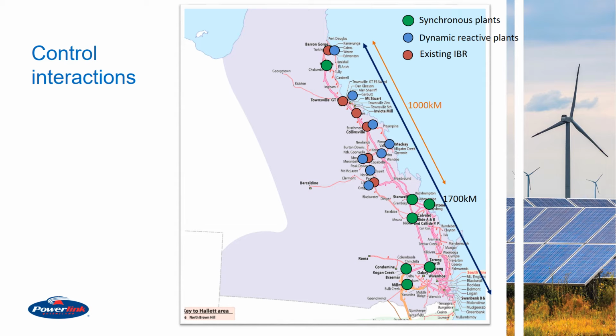One of the main issues that we have seen in Queensland due to low system strength, and that is not really any different from rest of the NEM, is the control interactions. What it means is that all those inverter-based plants interact with each other and cause some sort of instabilities. When we look at this diagram, the number of SVCs and the IBRs in one area, it's no surprise why we see the control interactions. And as we add more and more plant, the system inherently becomes weaker and the possibility of control interactions increases.